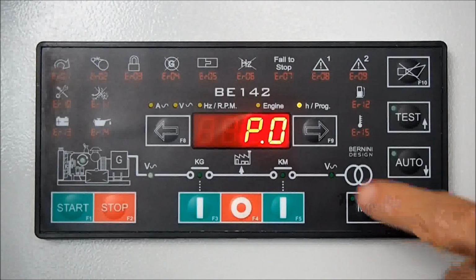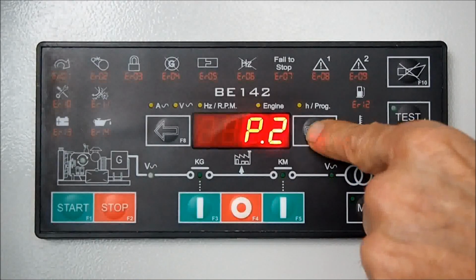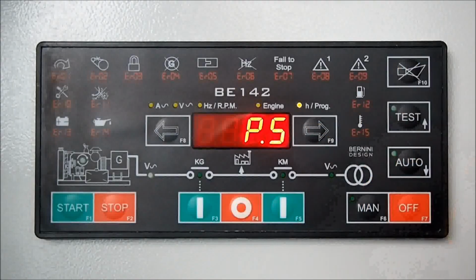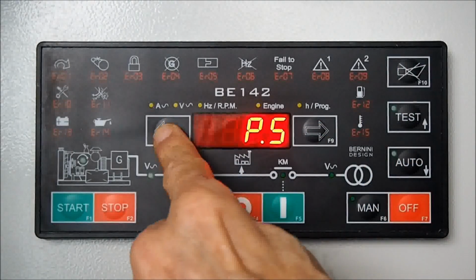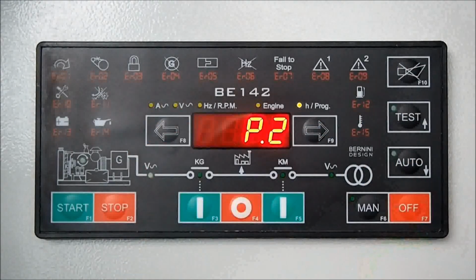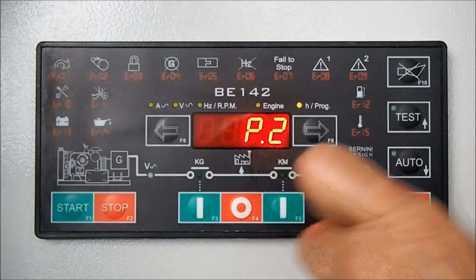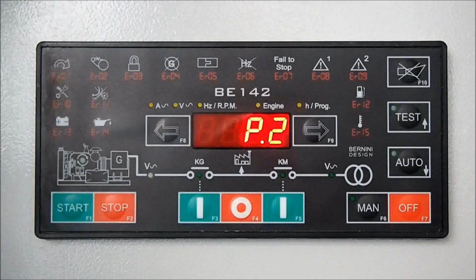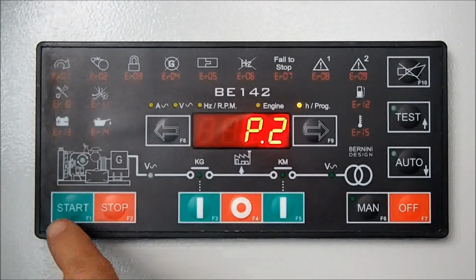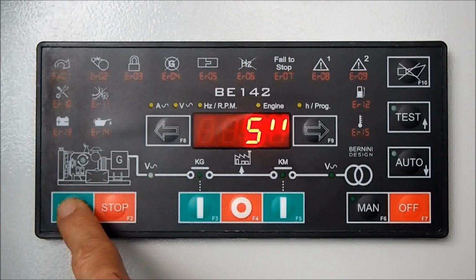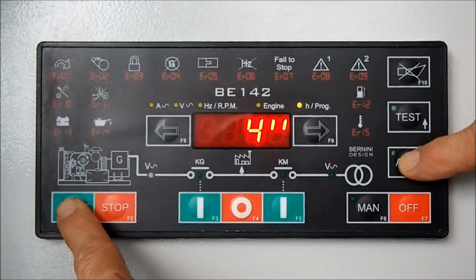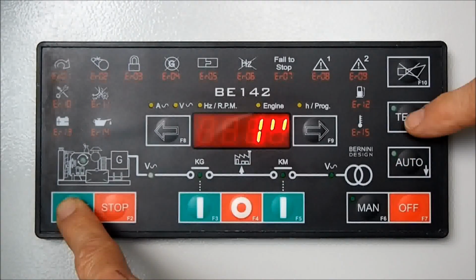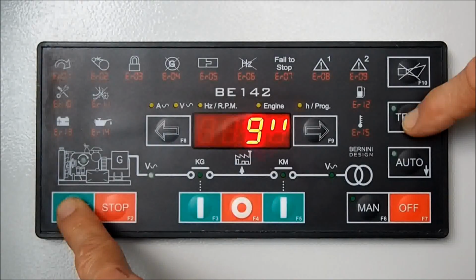By pushing F9, you go up the list of the parameters. By pushing F8, you go down through the list. Let's modify, for example, the parameter P2, that is the mains restore time. Push Start. The display shows the default setting, 5 seconds. You can go down with Auto, you can go up with Test.